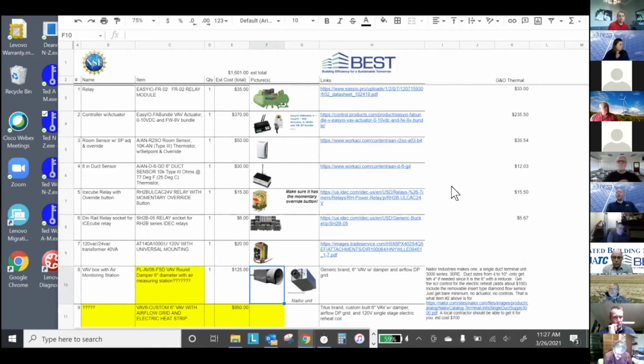It has a built-in pressure sensor, which is kind of where the specialty with VAV controllers usually applies. Some have a built-in actuator; this one does not. The reason we push the Sedona programming environment is because it's free and open source. Companies that make the controllers typically provide free programming software, and it's a convenient block-based programming system, which is the predominant programming style for the HVAC industry at this point.